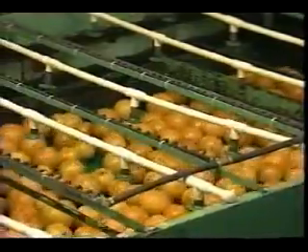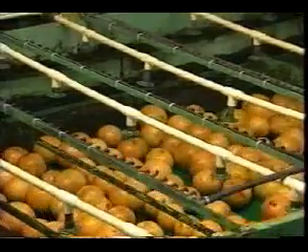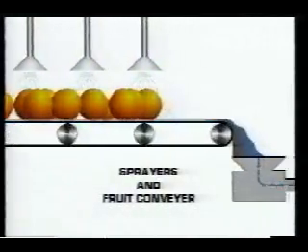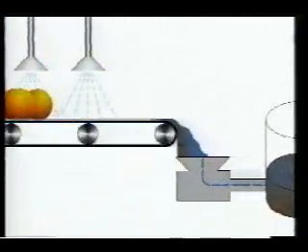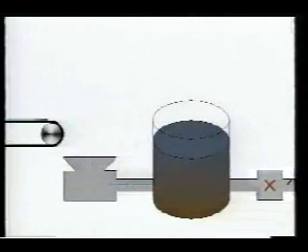The discharge of contaminated wastewater is eliminated, and the need for additional water is minimal since the only water lost is due to evaporation and filter backwash. Keep in mind that each system is custom engineered to meet a facility's needs, but the method of operation is basically the same. The water used to spray the fruit is collected as it flows into the drain pans. This water is piped into the main sump.